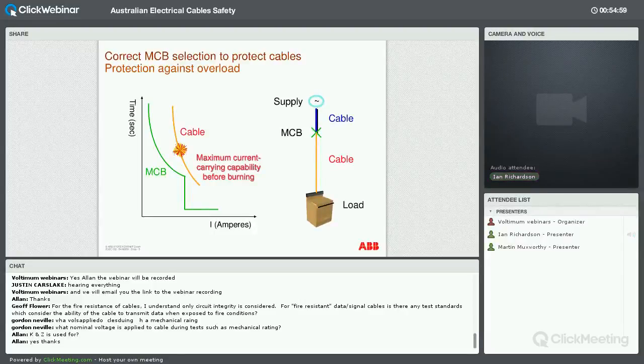Here we have a current carrying capacity or the capability before the cable starts to burn. And I can remember giving a similar presentation to this to a consultant in Perth, and it almost seemed like his favourite saying was, if you get it wrong, the cable burns. And it just rolled straight off his tongue. So he appreciated how important it was to get your circuit protection correct and protect these cables. Otherwise, the whole installation's under threat, and the cable potentially can virtually catch fire, depending on the characteristics of the cable, of course.